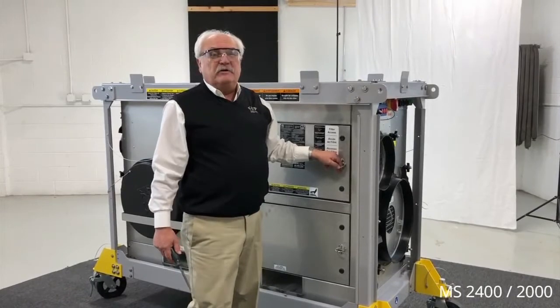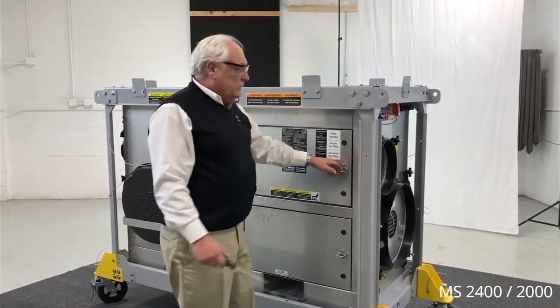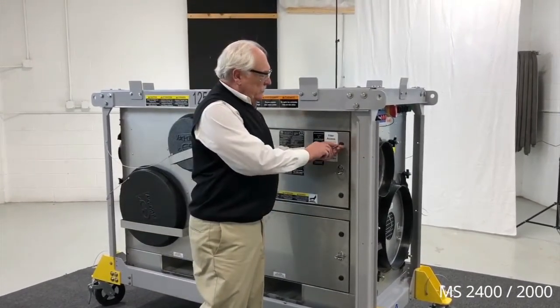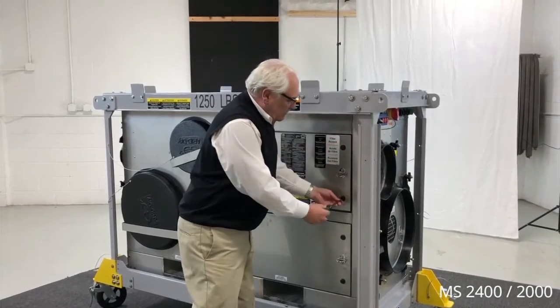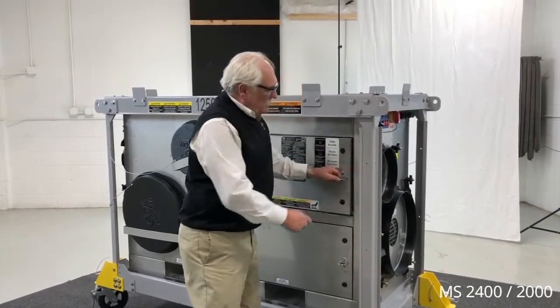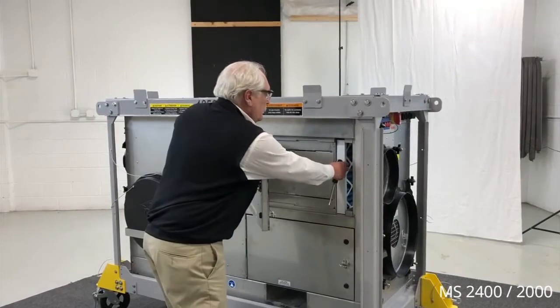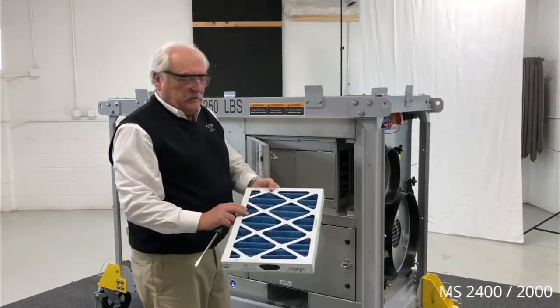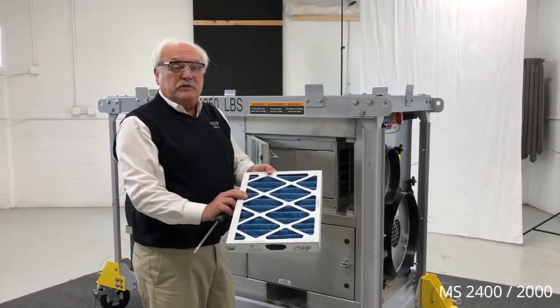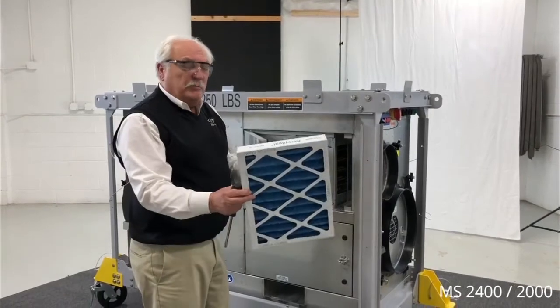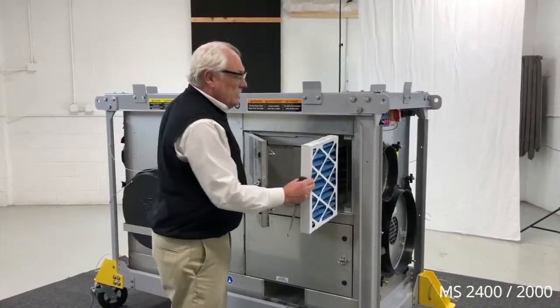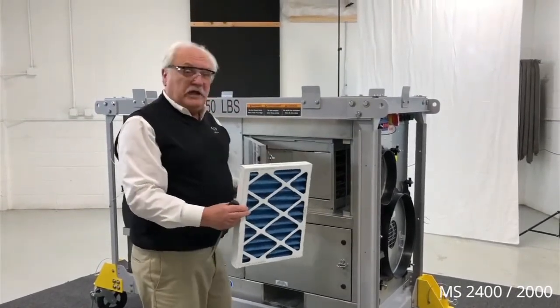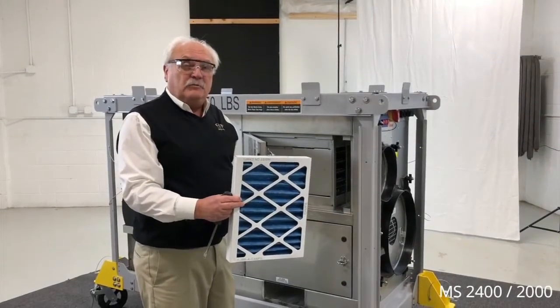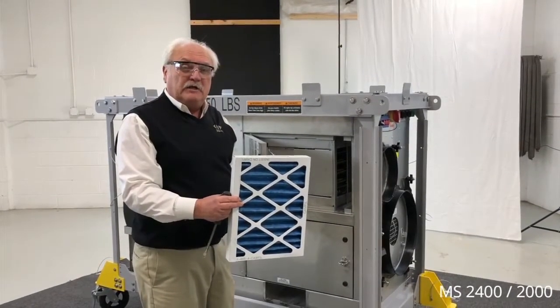Filter maintenance is very important to protect the desiccant wheel. To inspect the filters, you open the quick connect doors. Open the door, remove the filter, and inspect. Dirty filters should be replaced immediately, and you can replace the filter and close the door. There's a filter compartment for the reactivation airstream and a filter compartment for the process airstream located on the opposite side of the unit.